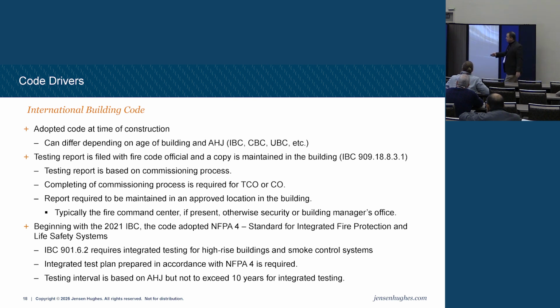What that means is when you're doing NFPA 4 testing, you better have everybody involved. Has anybody been a part of fire alarm testing where you know it's going to recall your elevators? You want the elevator contractor there, right? Flowing a sprinkler system should trip a fire alarm. That's the right way to test a sprinkler flow. I have to flow water. I want a sprinkler contractor there, because the fire alarm guy might say, oh, I know how to reset it if we have any problems with the sprinkler. Let's not trust that. Let's get the sprinkler tech there. So NFPA 4 pushes that logic: test everything, test it all together, and have all the people relevant to the testing be there.